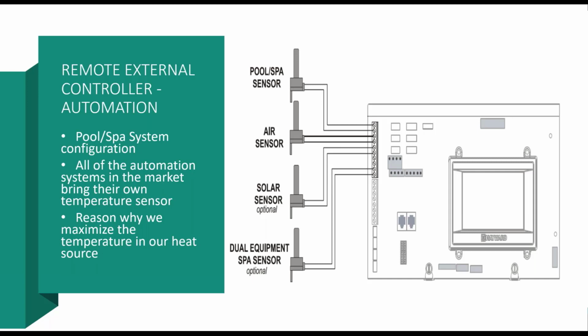Okay, they have a pool and spa sensor, that is the water sensor, and an air sensor, especially used when the automation system is installed in cold climates. Here in California we don't have that issue, but anybody else attending this class who might be in a place that is cold in winter, the air sensor is a great addition. And the solar sensor is used if you are using solar in combination with any source of heat, which can be a heat pump or a gas heater. So those automation systems are always going to bring those sensors.